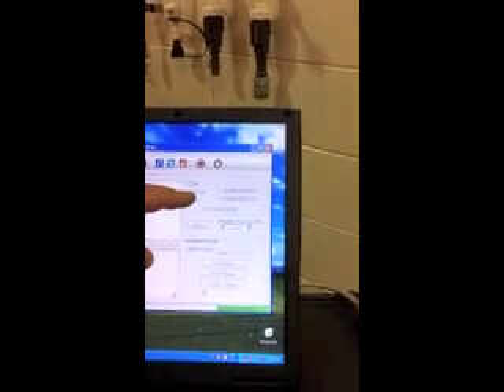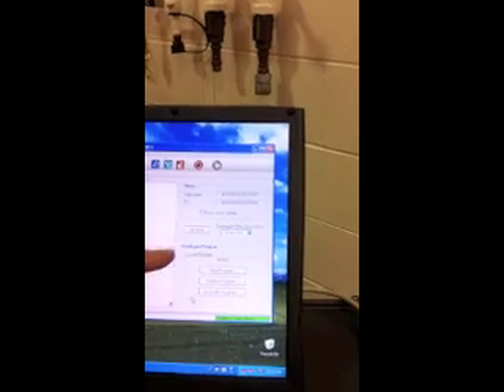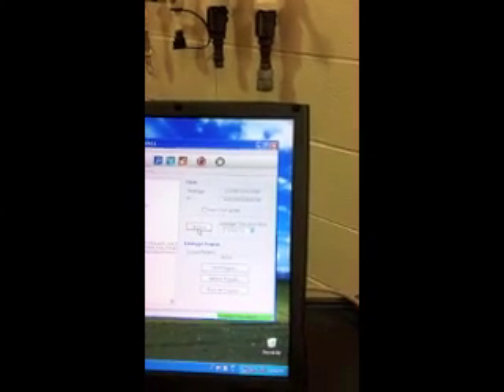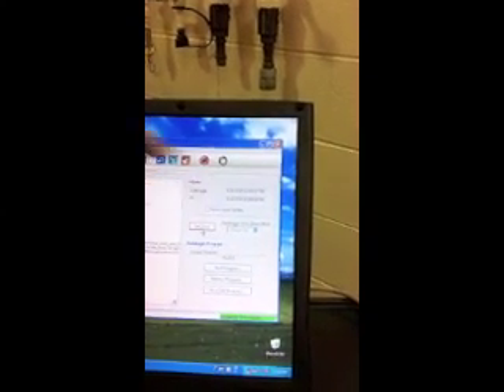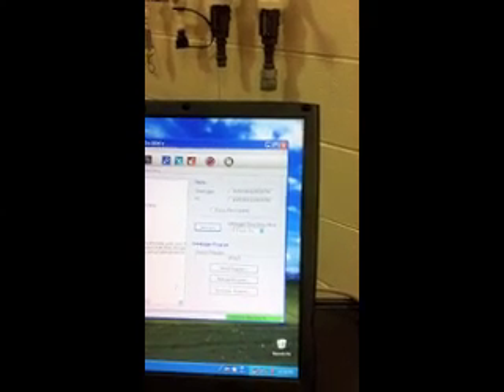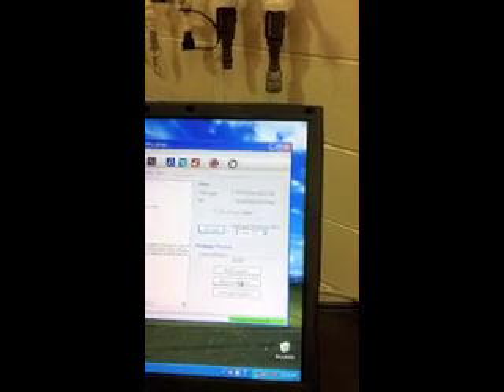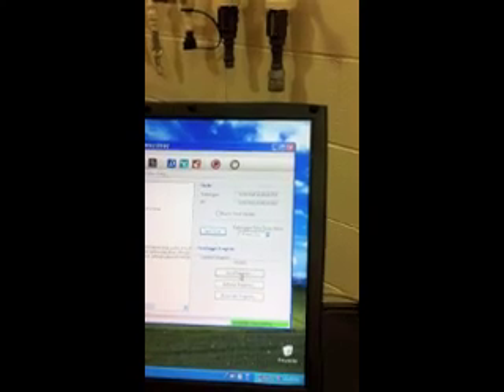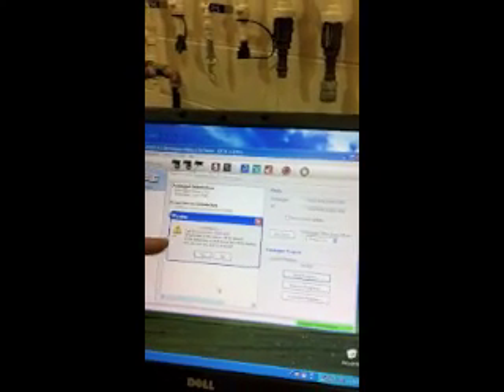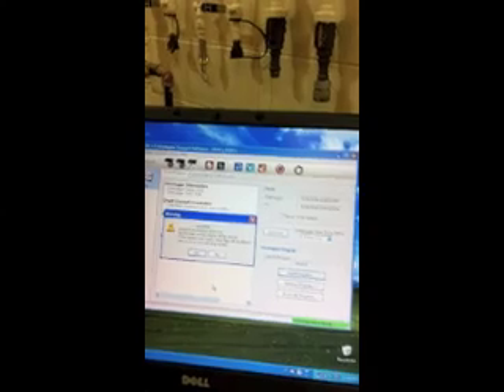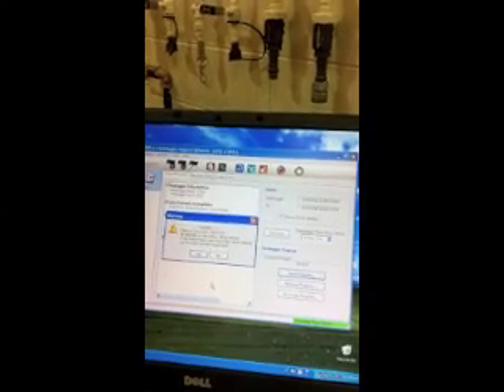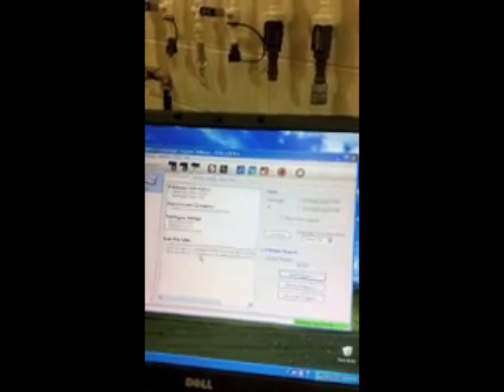So now we need to tell the data logger that's the time. So you click set clock, and you notice the data logger then updates to the same as the computer. And now all we have to do is send the program. You click send program. Here's a warning that it'll overwrite all of your data, which is fine because there's no data on it. Click yes.